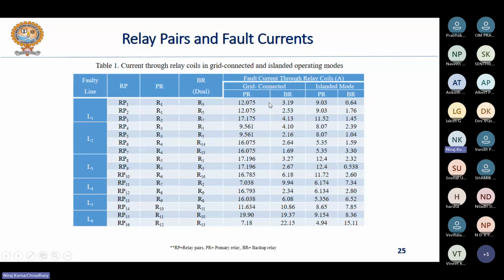So you can see that there is a difference in the magnitude of current flowing through the relay coils in both the modes of operation. In all the cases, you can see that the current flowing through the relay coil in grid connected mode of operation is higher than the current flowing through the relay coils in the islanded mode of operation, right? And based upon the same concept of the formulation of the primary and backup relay pair, we have formulated the different relay pairs.